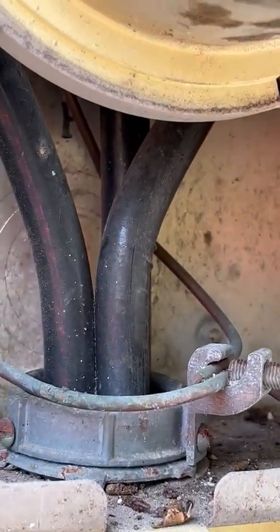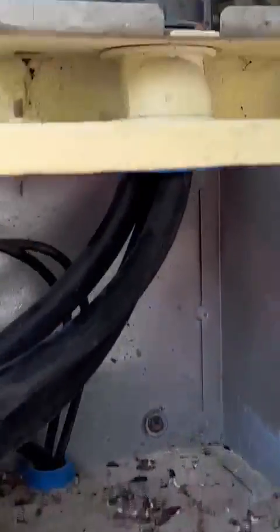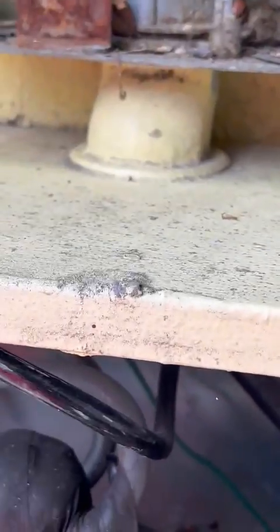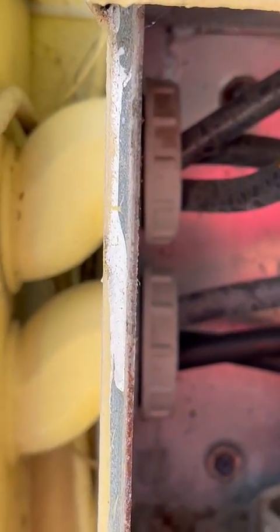I can see it's got at least 2 ought or 3 ought copper that comes into the meter. And then from the meter, he has a bit thicker wire that goes into a gutter. I can see the gutter doesn't have the weather protection right here. How do you call it? Neither one of them, neither this one right here, has the weather protection on it.